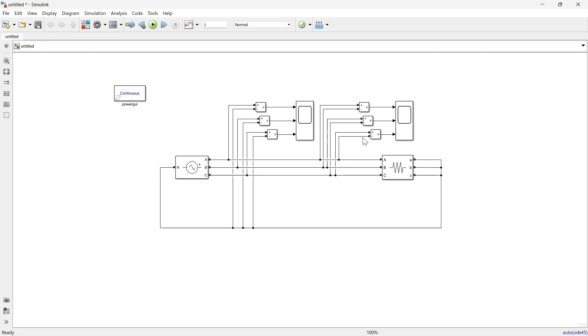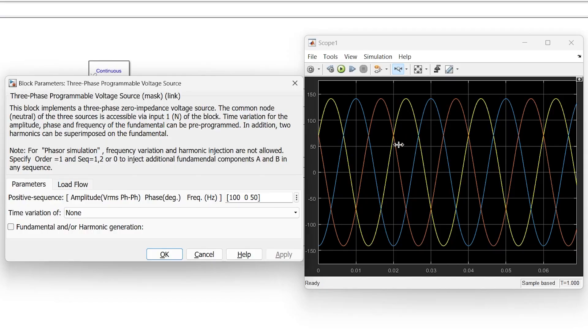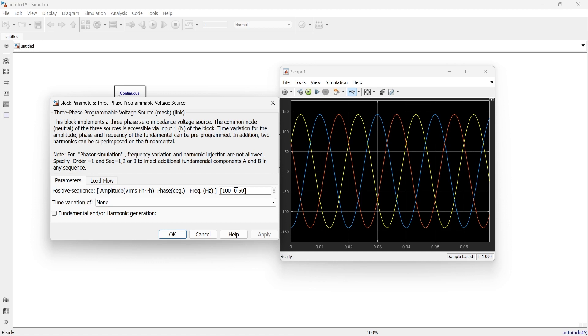I've connected this as a line voltage measurement. Now let's run. The amplitude we applied is 100 V RMS, and you can see that the peak is almost around 145 V — so the RMS is 100 V, which confirms this is the line voltage. The phase delay provided is zero.